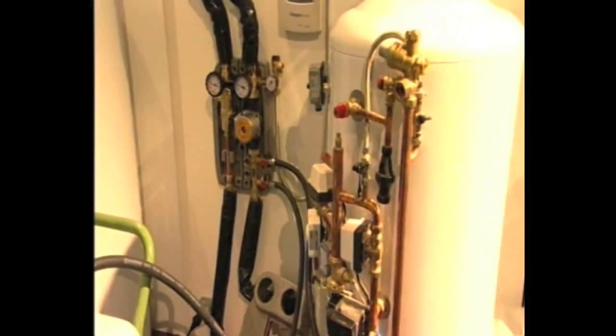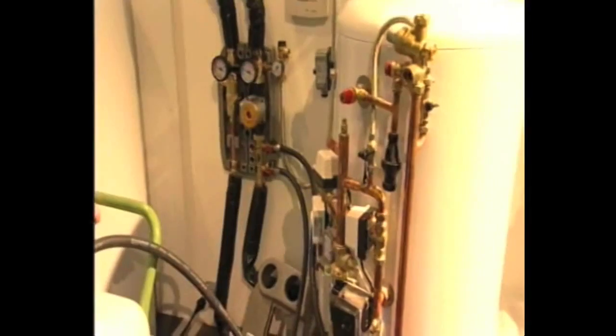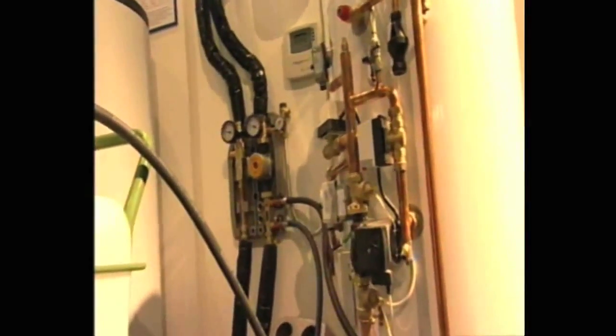So this is really all there is to the system. And we're looking at a 30-tube system heating up to 300-litre cylinder for a family of up to five people. And that will give, we typically aim for 55% plus of the contribution across the year.